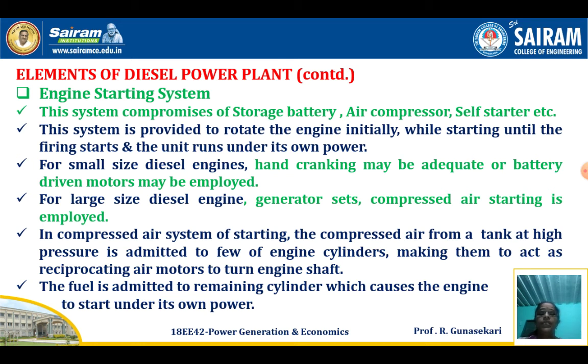In the compressed air system of starting, compressed air from a tank at high pressure is admitted to a few of the engine cylinders, making them act as reciprocating air motors to turn the engine shaft. The fuel is admitted to the remaining cylinders, which causes the engine to start under its own power.